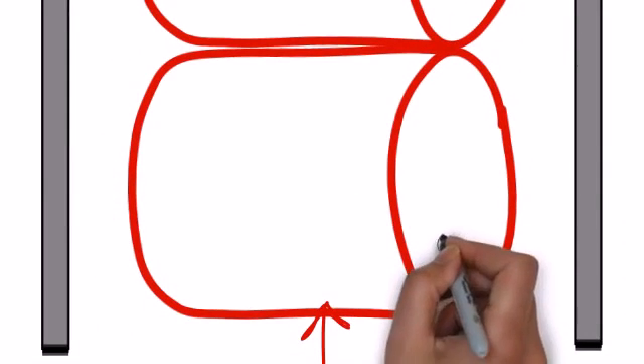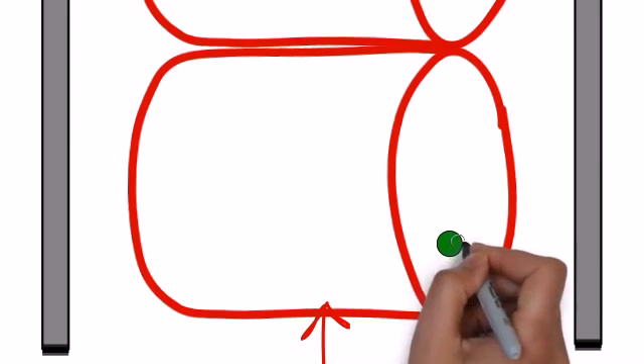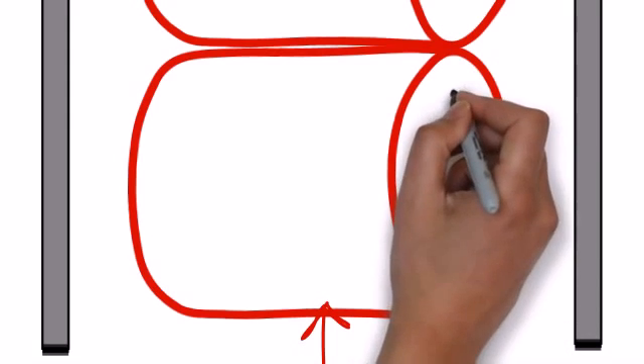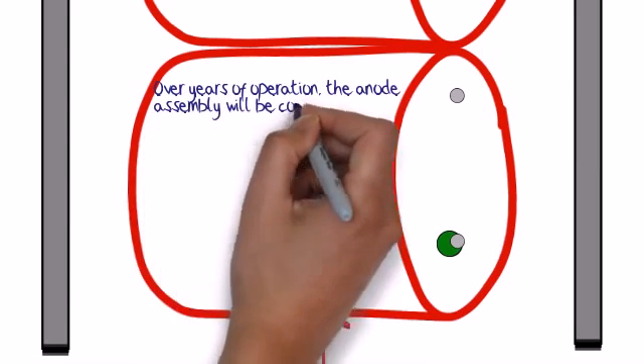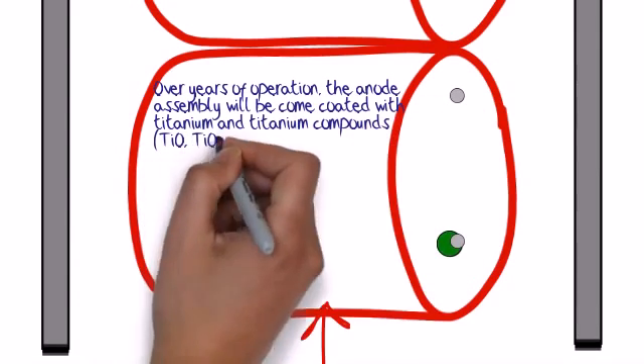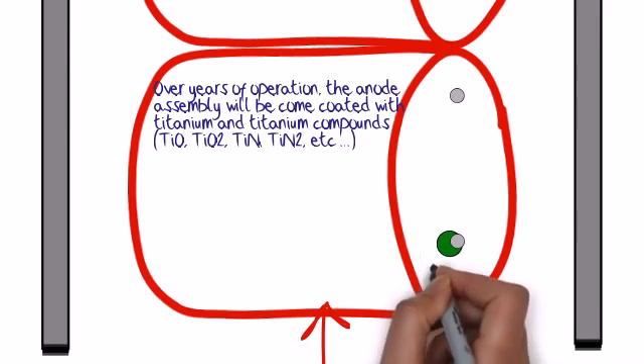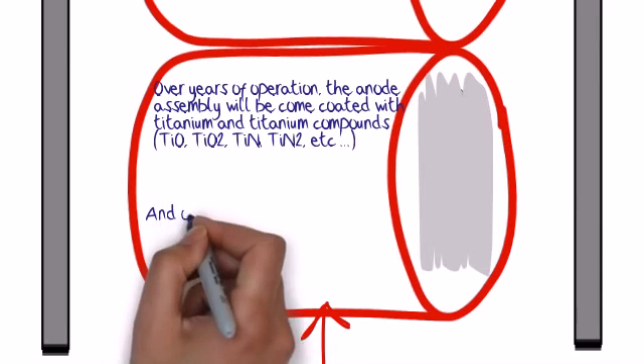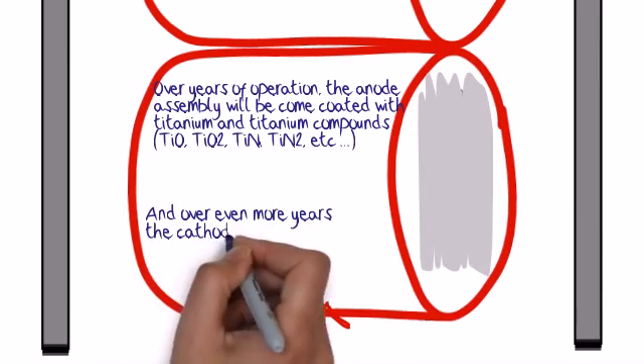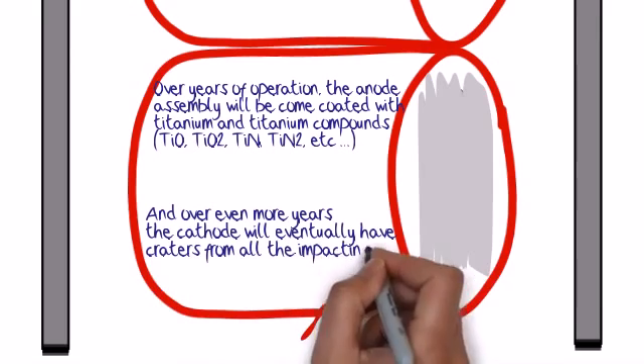And over time, enough molecules are going to sputter onto that titanium that you will actually have a buildup of those titanium compounds and titanium directly all over the walls of those anode tubes. And over the years, that cathode will eventually have craters form from all the impacting ions.